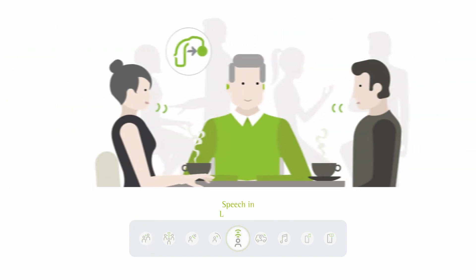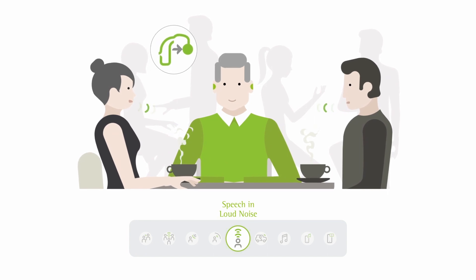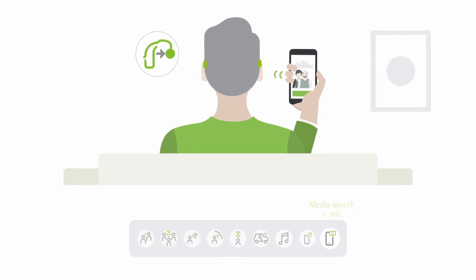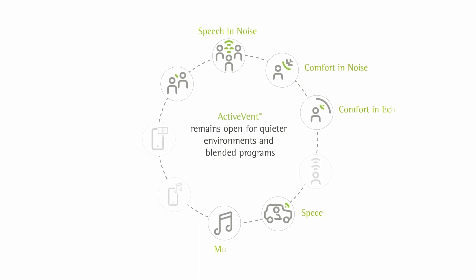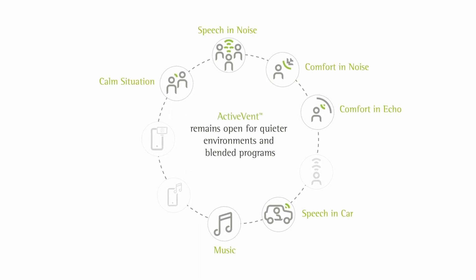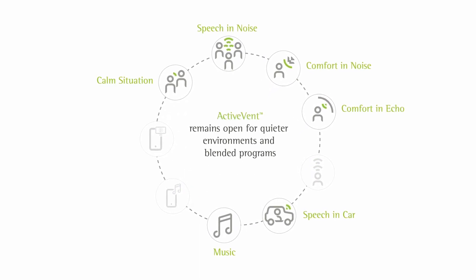However, when the environment is assessed as speech in loud noise or streamed media content, the vent will automatically close. So ActiveVent will remain open for quieter environments or blended programs, and it will automatically close in the speech and loud noise and streaming programs.